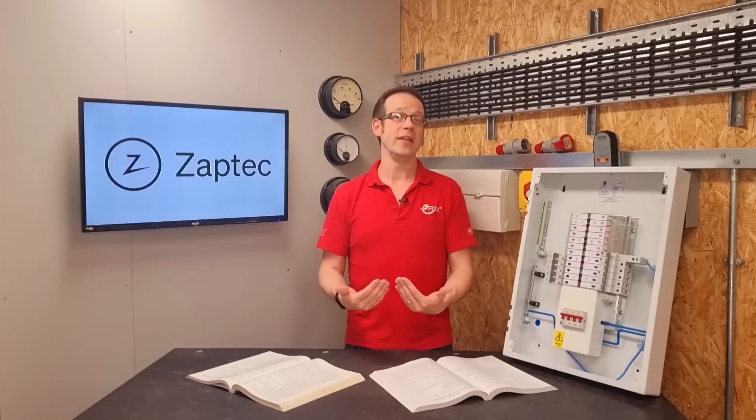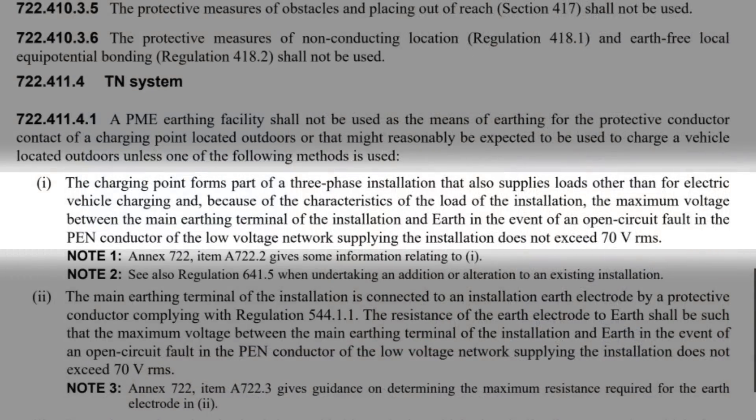However, that brings us nicely on to the end of the old indent we just read because it gives this little caveat: because of the characteristics of the load of the installation, the maximum voltage between the main earthing terminal of the installation and earth in the event of an open circuit fault in the PEN conductor of the low voltage network supplying the installation does not exceed 70 volts RMS.